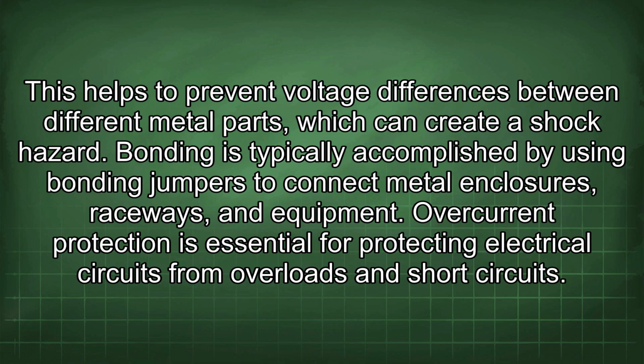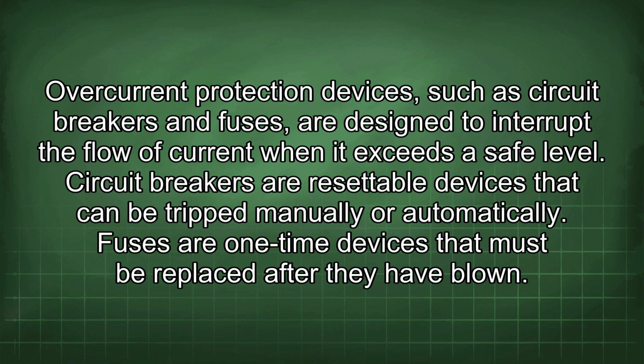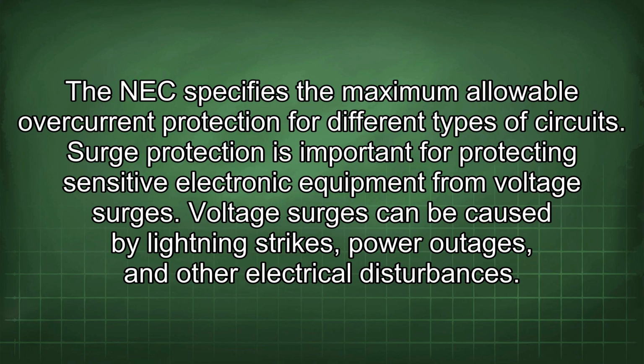Overcurrent protection is essential for protecting electrical circuits from overloads and short circuits. Overcurrent protection devices, such as circuit breakers and fuses, are designed to interrupt the flow of current when it exceeds a safe level. Circuit breakers are resettable devices that can be tripped manually or automatically. Fuses are one-time devices that must be replaced after they have blown. The NEC specifies the maximum allowable overcurrent protection for different types of circuits.